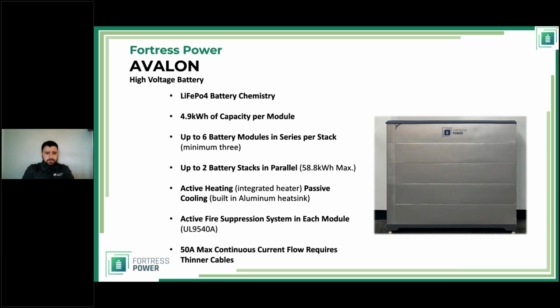Also, because these modules are connected in series, this is a high voltage battery. That means when you're choosing or connecting the battery power cables, you can go with thinner cables, because the current will naturally be less to obtain the same capacity compared to low voltage batteries.